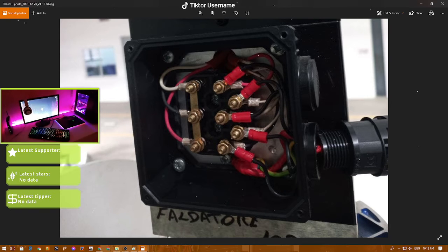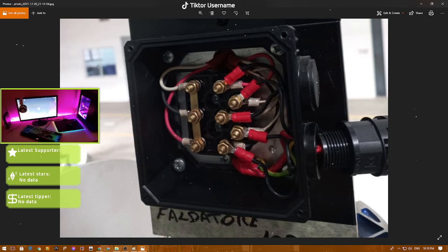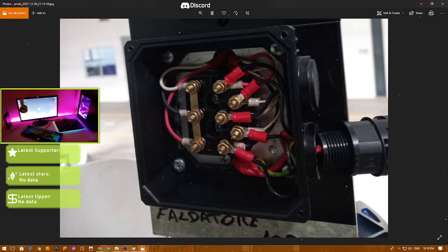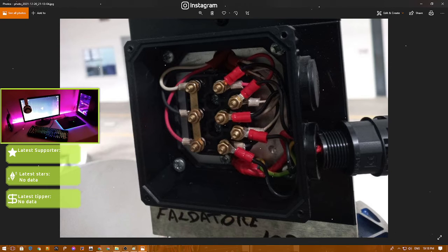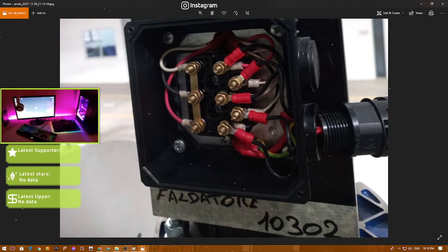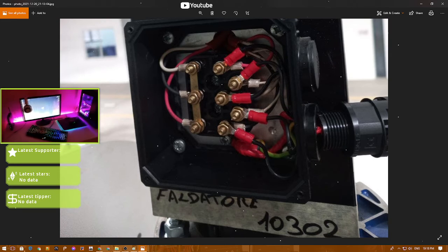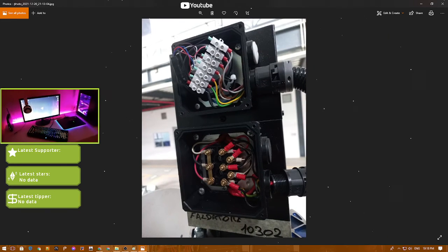I take the signal from here. We can use a relay at only 12 volts, with a small current, and then we use its NO/NC contact to control the contactor, and the contactor's power circuit is 200 volts to control the brake like this. You will understand what I mean. And this one is the earthing or grounding protection for the device when there is a short circuit.